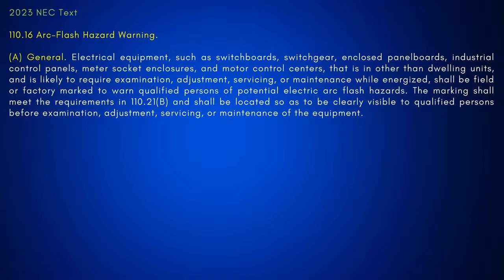Well, the same language is right here. They're recognizing the type of equipment you're going to work on, and they say, and is likely to require what? Examination, adjustment, service, or maintenance while it's what? Energized. And if that's the case, it's required to be field or factory marked to warn qualified persons of potential electrical arc flash hazards. Okay. Yeah, and I can see why a 4-year-old couldn't read that. You know what I mean? Like if you put it on a label.